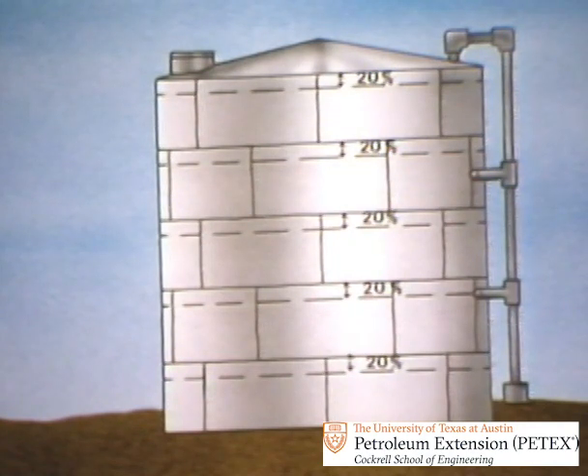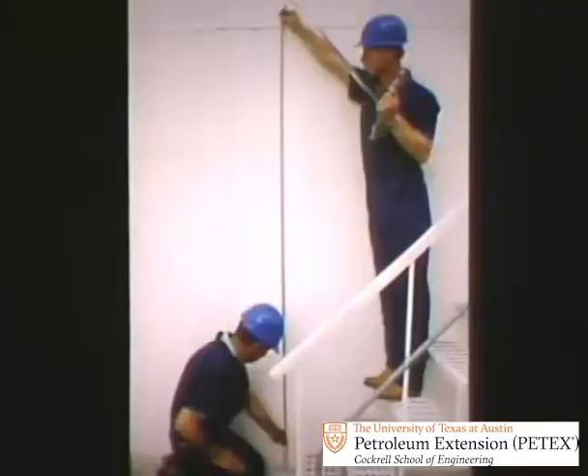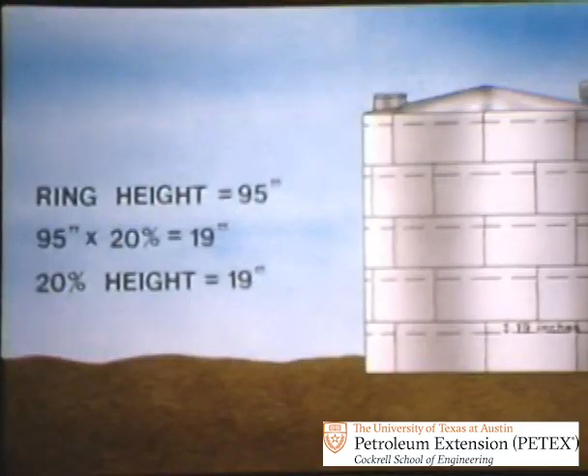For example, when the crew measures the height of the bottom ring of this tank, they find that it's 95 inches. 20% of 95 is 19 inches, so the tape has to follow a path around the ring 19 inches from the top.